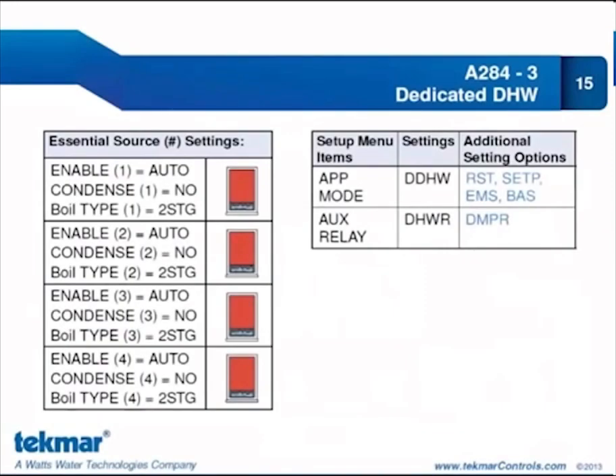The essential settings for application 3: in the source menu, all four boilers are non-condensing two-stage. We enable each by selecting auto, condensing is no, and boil type is two stage. This is a perfect situation to use the copy feature from boiler 1 to boilers 2, 3, and 4. The other two essential settings are in the setup menu: the application mode is dedicated domestic hot water, which allows only one water temperature for the fixed set point of dedicated DHW. The auxiliary relay is configured to control the domestic hot water recirculation pump, not damper.